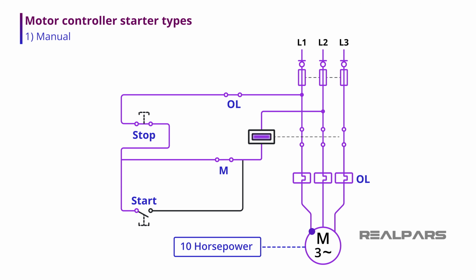Now that I've described the four major categories of motor controller by starting method, I will now describe the six major motor starter types. The first is manual motor actuation, which requires an operator to switch the motor on and off. Due to safety considerations, manual motor starting is limited to motors of 10 horsepower or less, but they can be used on single or three-phase applications.